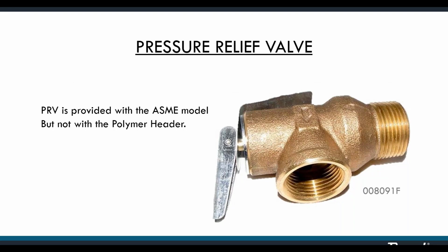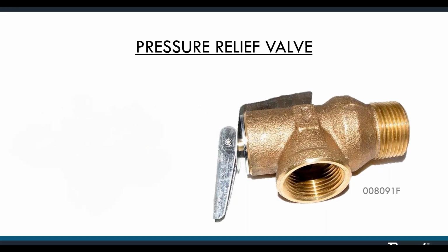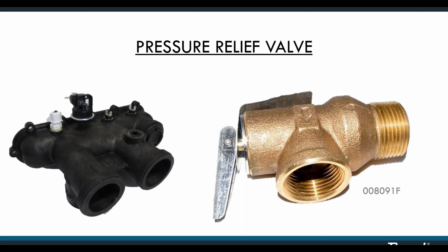The PRV is provided with the ASME model in order to meet ASME compliance, but we don't provide one with the polymer residential model. We do provide a port for installation in case you need to install one. We're going to leave that up to you. That port has a threaded plug that can be removed with a 1/2-inch drive socket wrench.